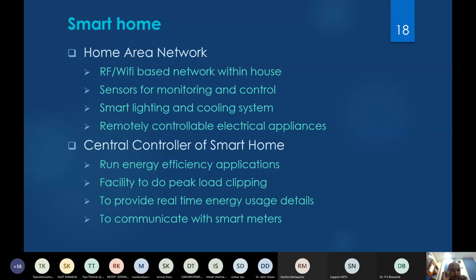This peak load shaving and valley filling can be implemented, but the enabler is that you must have control over the load—that's the first prerequisite. Of course you also need a communication medium, but first the load should be controllable. This is enabled through Wi-Fi switches, so we can control loads remotely as well as locally. We took a declaration from the inmates on whether we could control their loads. This is how we implement demand response.